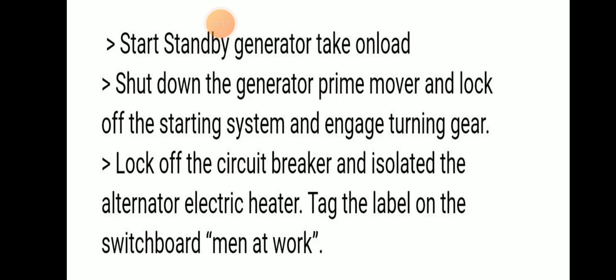Today we will be discussing the procedure for alternator overhaul. So we have to start by starting the standby generator and taking it on load. Then we have to shut down the generator prime mover, lock off the starting system and engage the turning gear. Then we have to lock off the circuit breaker, isolate the alternator electric heater, tag label on that place, and place a placard, men at work board.